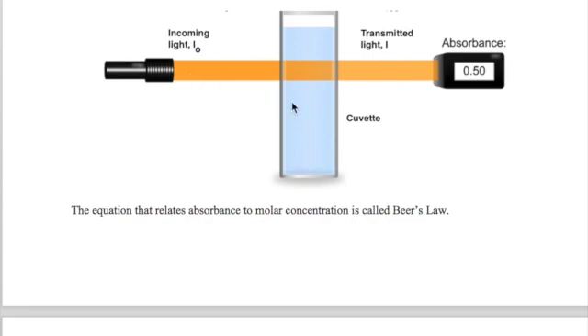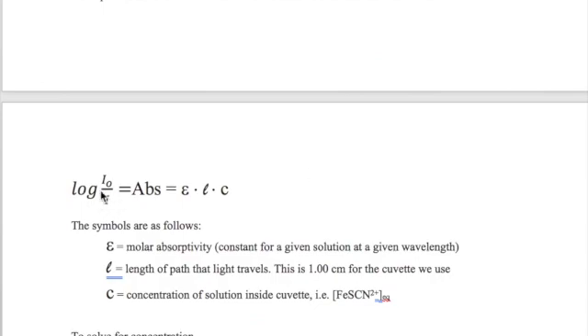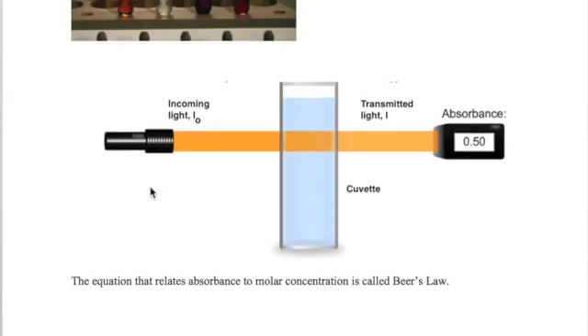When an incoming light strikes a solution, some of that light is absorbed by the solution. The transmitted light will have a reduced intensity. The absorbance can be calculated as the log of the intensity of the incoming light, I0, over the intensity of the transmitted light, I. The solution is placed in a fairly transparent container called a cuvette. This absorbance value is automatically shown on the spectrophotometer, for example 0.5 in this case.